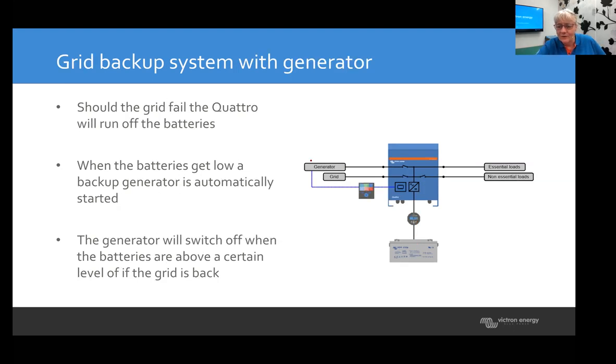In this scenario, when you couple it with a backup generator: first the grid stops, you get power from the battery, and if the battery gets low, we send a signal to the generator, which will start, recharge the battery, and feed the load. So you can easily have a grid connection and a backup generator with an inverter charger as backup. First line of defense is your normal inverter charger; once that runs out because the battery is empty, then you start the generator. So that's possible, for instance.